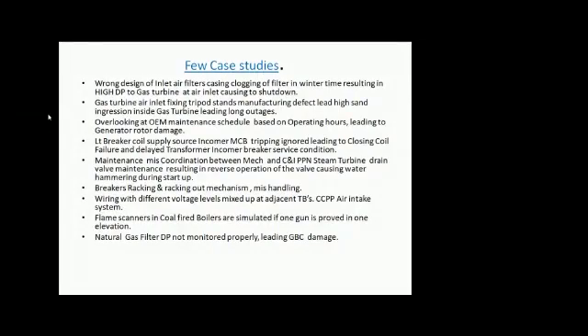So this is one thing, and coming to the other point. Because of that, what happened in one power plant during peak winter time was that the filter DP went very high, because of which the gas turbine could not receive a sufficient quantity of air. Because of that, the machine had to be shut down during the early morning hours and started again after the sun was hot. So like that, design issues can crop up.